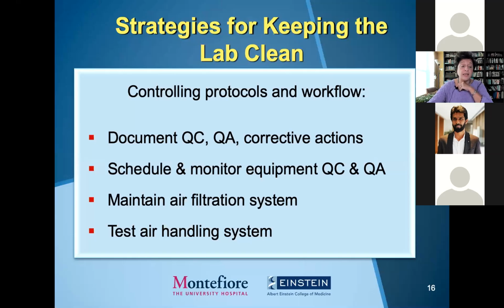The following is a list of possible QC and QA protocols that may be used to create a personalized QM program, so you can document all QC, QA, and corrective actions in order to provide transparency and traceability. Create a program to reduce or eliminate hazardous materials such as mercury thermometers, sterilizing products that contain ethylene oxide, betadine, or are otherwise embryotoxic. Schedule and monitor equipment QC and QA.